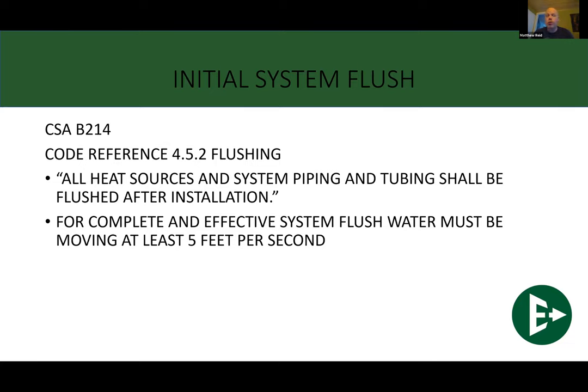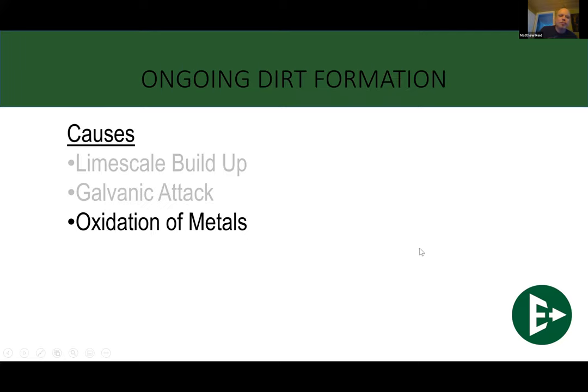I've seen some commercial jobs with 5-inch piping where I've seen gloves come out of the piping when we do our flushing. And if we don't get it out the first time, the worst case scenario is it's going to get stuck, usually in one of the air bleeders, as it's popping out of a system. And if that air bleeder gets stuck open, then fluid is going to be popping out for the whole duration, while the system is unattended. So flushing is super important. Make sure that you get in it, move that water, move it fast.